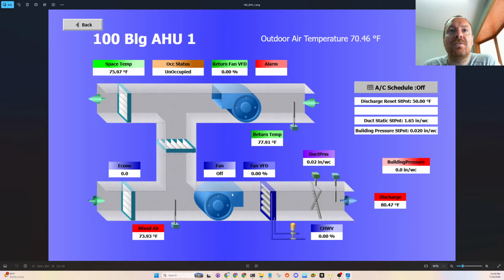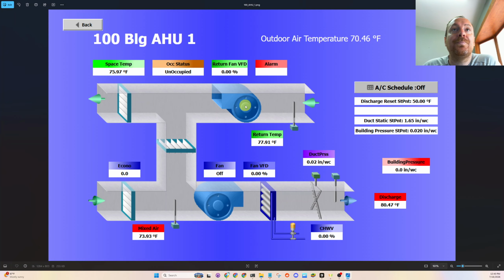These big fans, just the supply fan, maintain this duct static pressure sensor, which would be somewhere in the building, usually 2/3 of the way down the duct stream. Big air handling unit, probably pushing multiple floors. So it's maintaining that duct static pressure, and most likely this return fan is just doing a speed offset of this one. Sometimes with Guideline 36, or sometimes they even put airflow measuring stations on these fans, or even mixed air pressure control. But usually the simplest way to do it is this one controls to maintain that duct pressure, and then this return fan just runs a fixed speed offset from that. Usually it's just like 10% less. They just throw that in there.